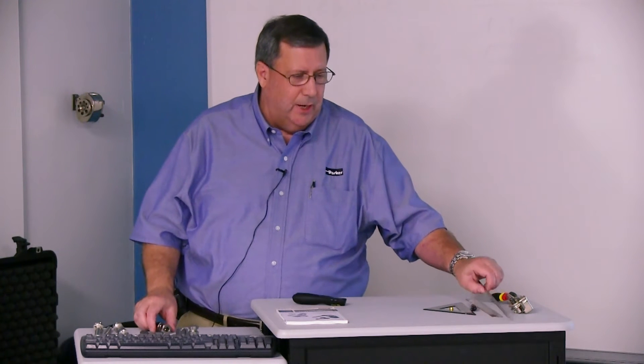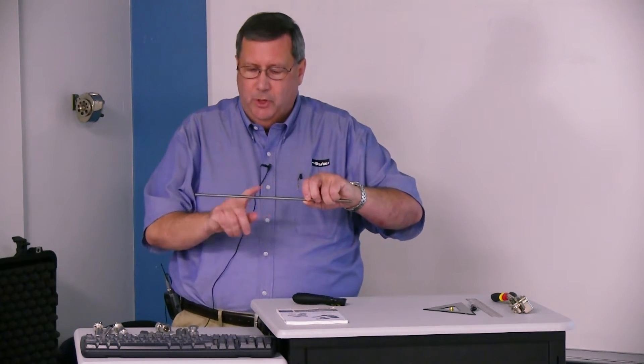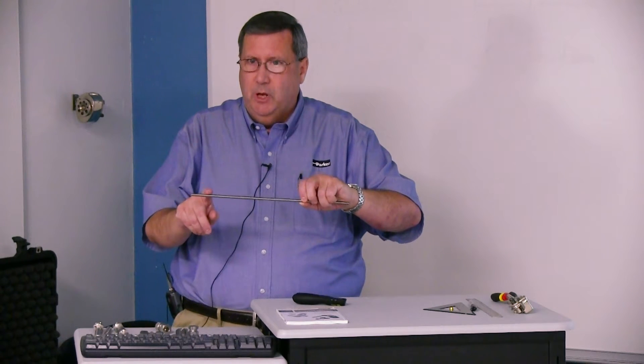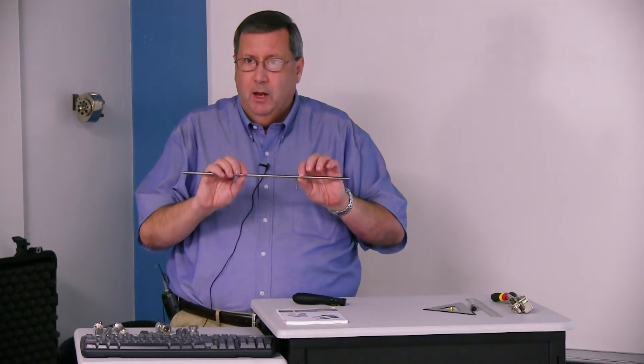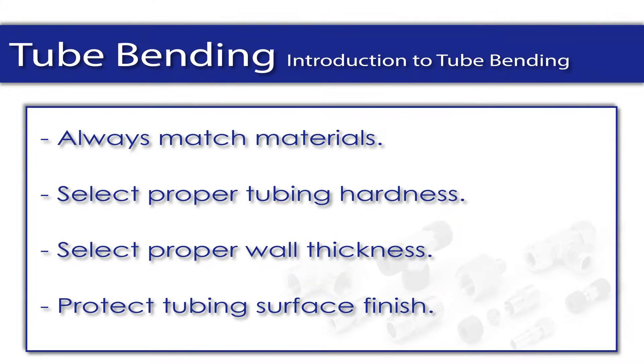First of all, we want to talk about tubing because a lot of times we talk about fittings and we don't talk about the sealing surfaces actually on the tube. That's a very important concept to know. You never know where your sealing surface is going to be on the tube, so you need to be taking care of the tube when you store it or prepare it. Things we want to talk about: always match materials, select the proper tubing hardness, the wall thickness, and the proper tubing surface finish.